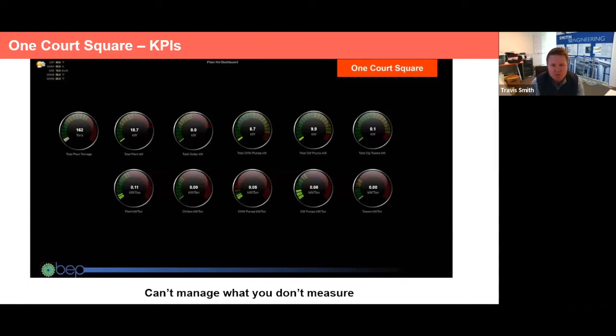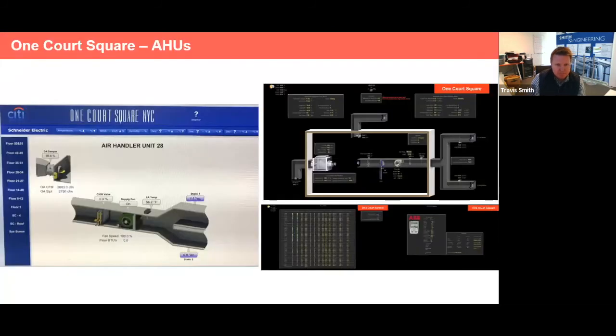This is important for the operators to be able to see how each individual component is performing. The dial turns yellow or red, and then it's time to investigate, hey, what's going on with my chilled water pumps? Maybe a strainer's clogged or something, but that dynamic feedback is critical for operations to maintain high efficiencies into perpetuity. Just an example of an air handling unit screen comparison, pre and post.